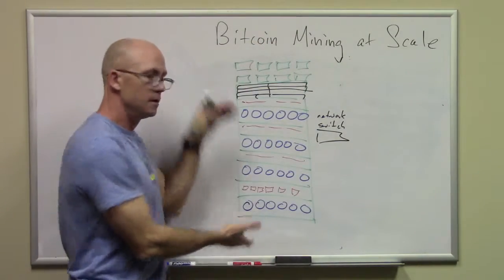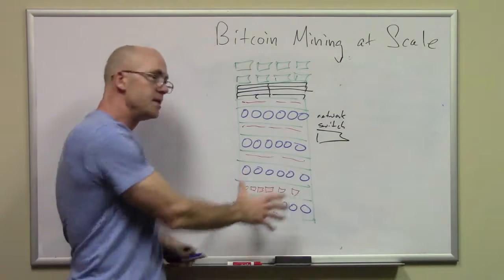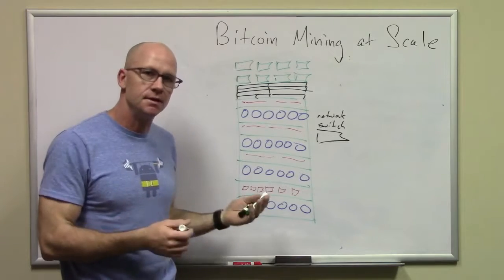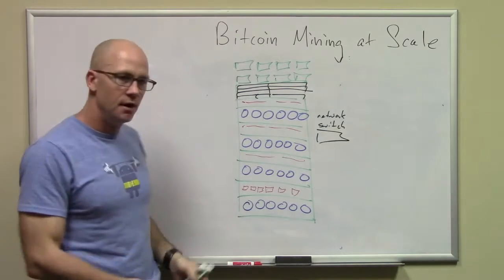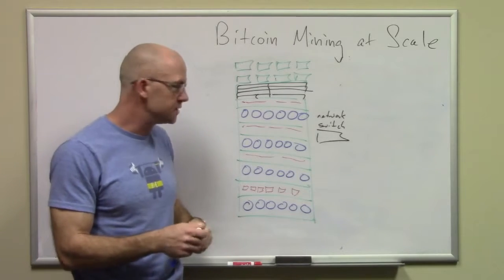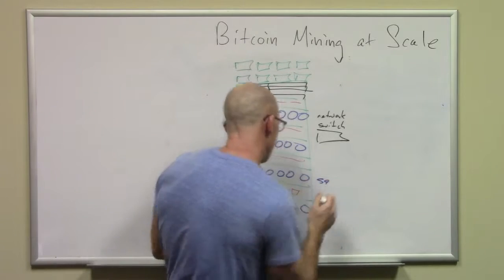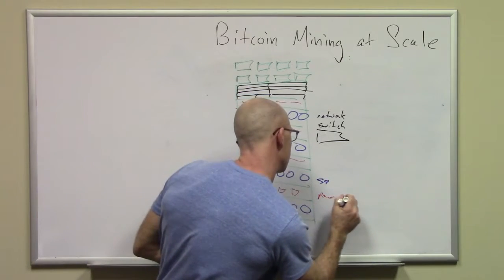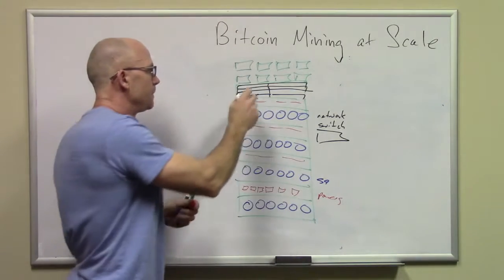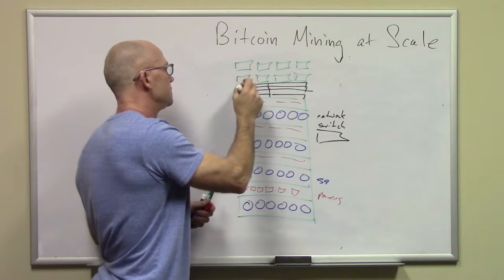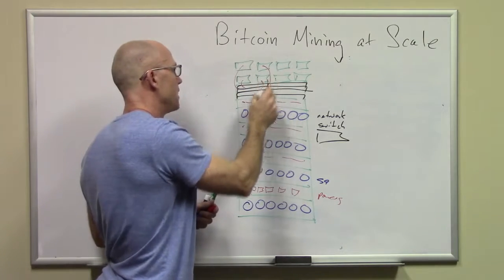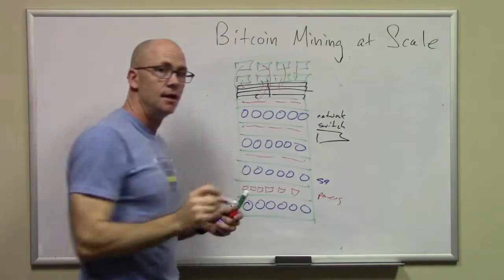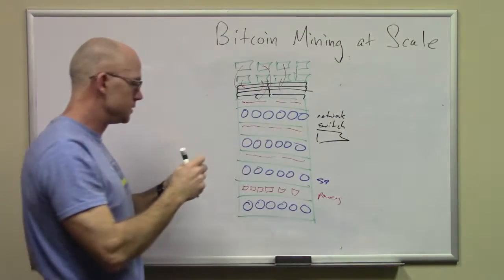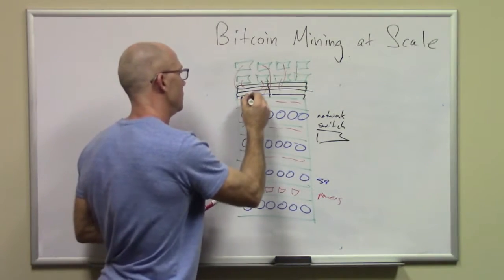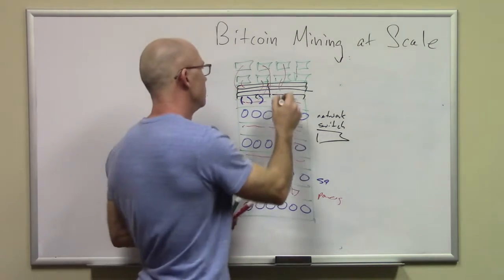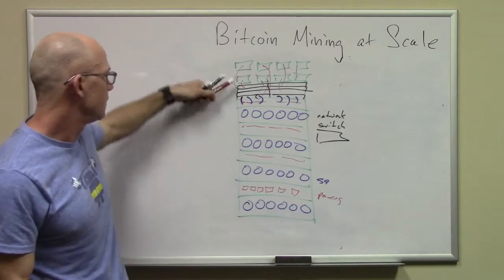Here in a typical environment we've got a very dense Antminer S9 deployment—24 in a single rack, and they're not all that big so you can fit these together nicely. These are the Antminer S9s, these are the AC to DC power supplies, and you're going to need, like I said, 8 power distribution units, and those PDUs each plug into one of those 30 amp connectors. So we've got 8 30 amp connectors coming into 8 PDUs, and from the PDUs we power 3 Antminers per PDU. It all adds up—we've got 4 shelves of them, 4 sets of PDUs.